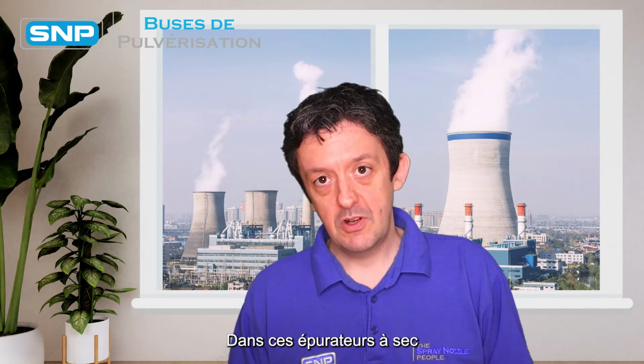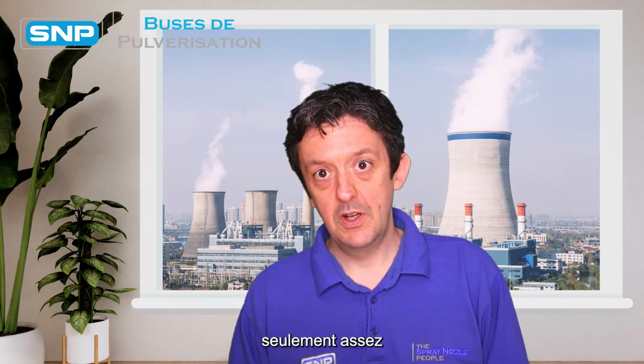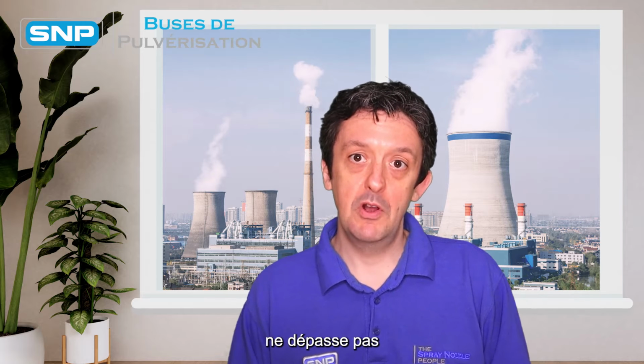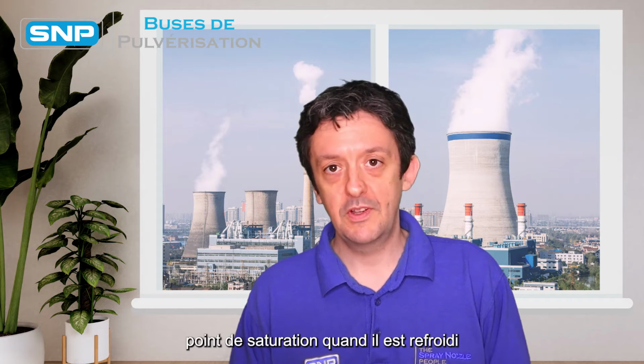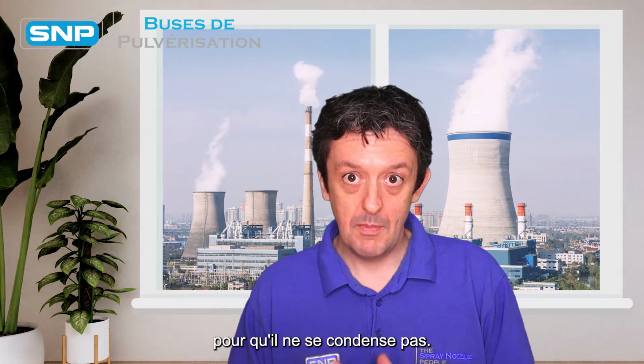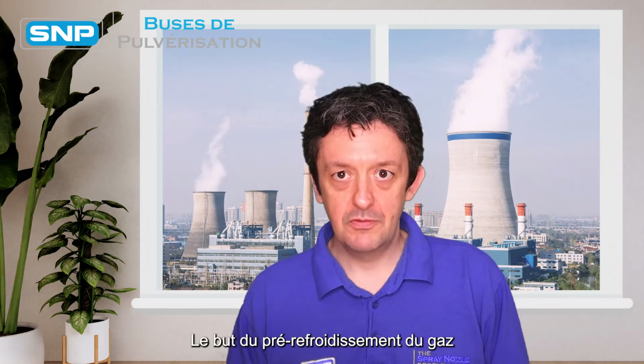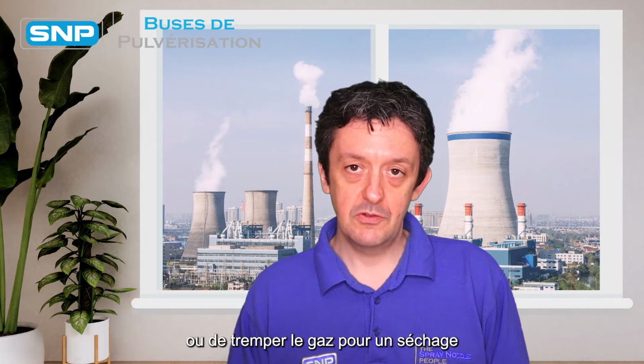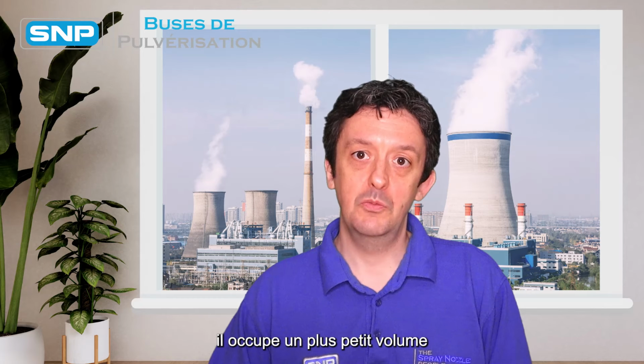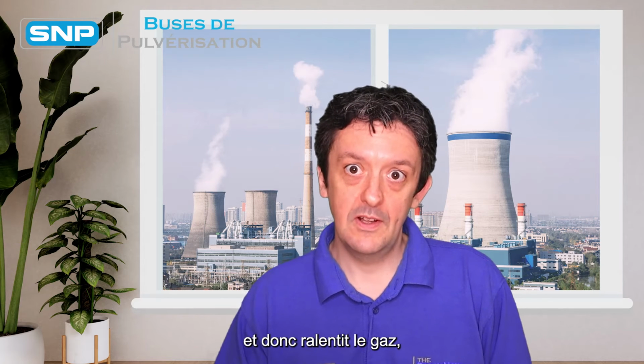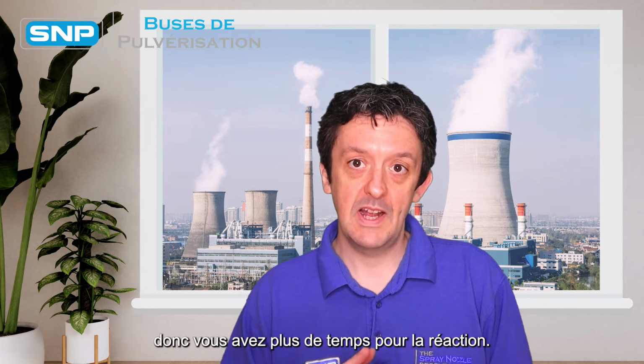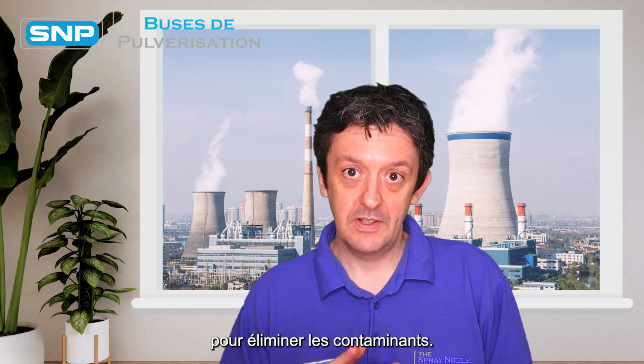In these dry scrubber designs, only enough water is put into the gas so that it doesn't reach oversaturation point when cooled, so it doesn't condense out, so that it remains dry. The purpose of pre-cooling the gas, of quenching the gas for a dry scrubber, is twofold. First, it contracts the gas down so it occupies a smaller volume and so slows down the gas flow, so you've got more time for the reaction to actually occur to remove the contaminants.